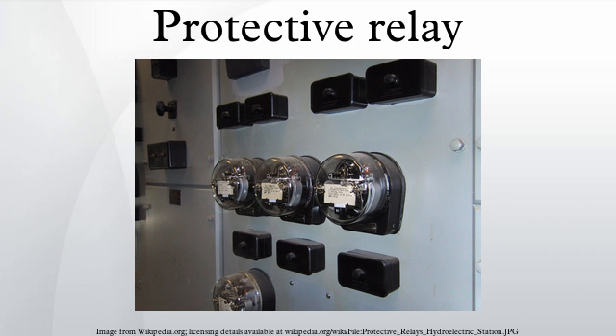The time taken for rotation to make the contacts is not only dependent on current but also the spindle backstop position, known as the time multiplier. The time multiplier is divided into 10 linear divisions of the full rotation time. Providing the relay is free from dirt, the metal disk and a spindle with its contact will reach the fixed contact, thus sending a signal to trip and isolate the circuit, within its design time and current specifications. Drop-off current of the relay is much lower than its operating value, and once reached the relay will be reset in a reverse motion by the pressure of the control spring governed by the braking magnet.